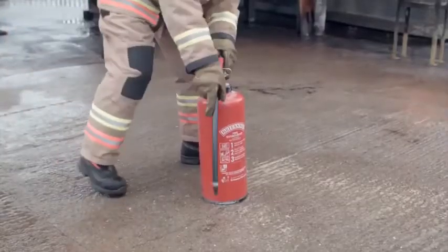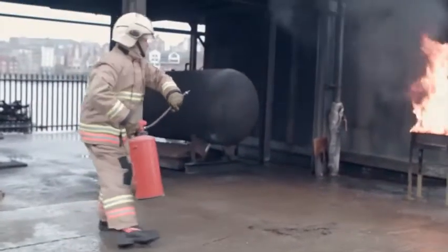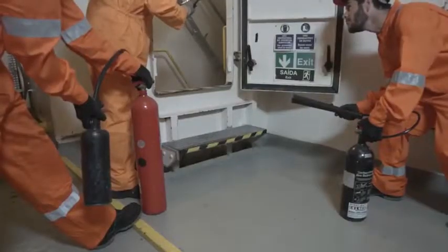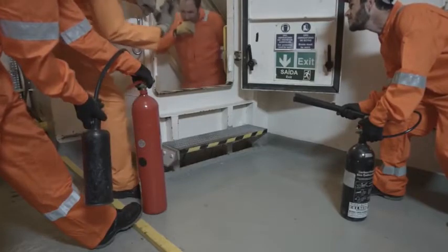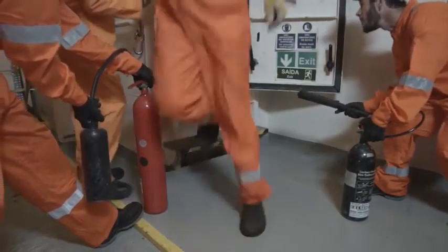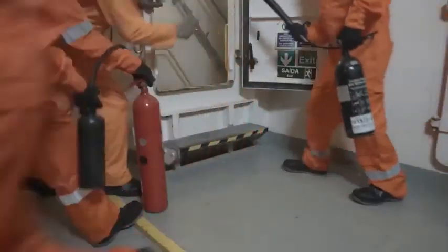We have seen that water extinguishers can increase the dangers of cooking oil fires, but they can also lead to electrocution when used on an electric fire. If more than one CO2 extinguisher is used in a confined space, the area must be evacuated immediately, as the level of CO2 will be above the requirement of 5% of the net volume of the space.